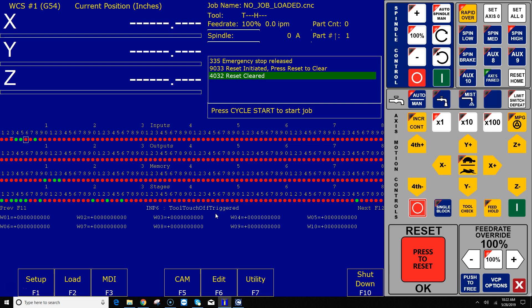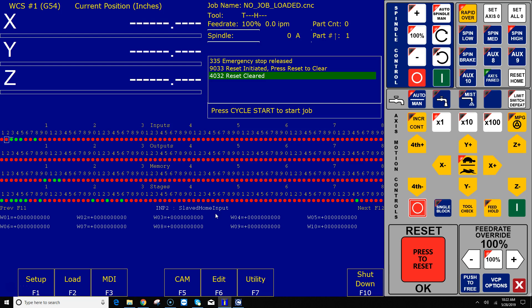Alrighty, let's go ahead and trip now the probe and you'll notice that it turns green when it's tripped. But look closely, it has a line above it, so that means that input has been inverted. It's been inverted to support a mechanical probe that is normally closed and opens the circuit.